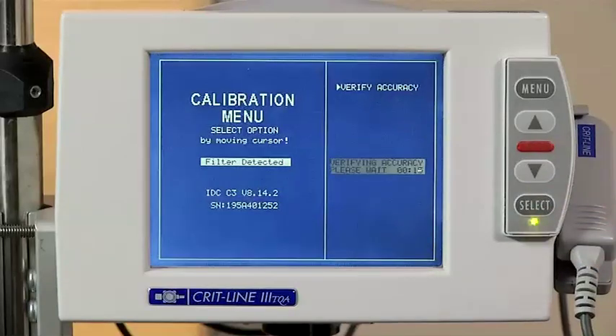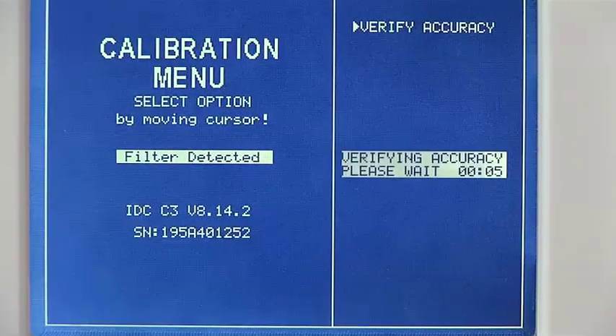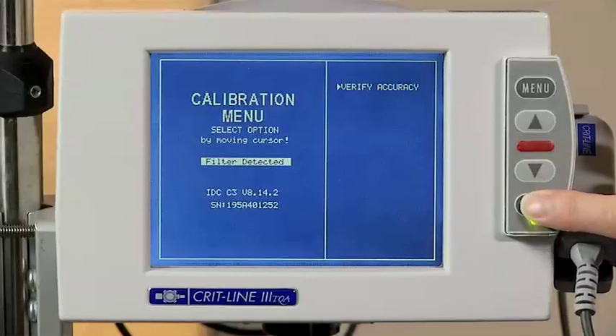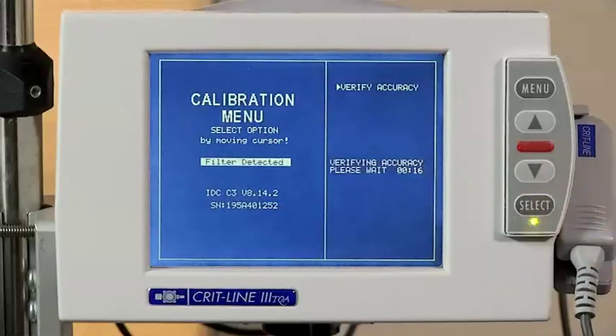Wait for the 2-minute countdown process. The elapsed time remaining will display. If the CritLine monitor indicates the Verify Accuracy test failed, you will be asked to confirm proper sensor placement, as well as ensure the filter is clean. Once this is done, press the Select button to repeat the Verify Accuracy test.